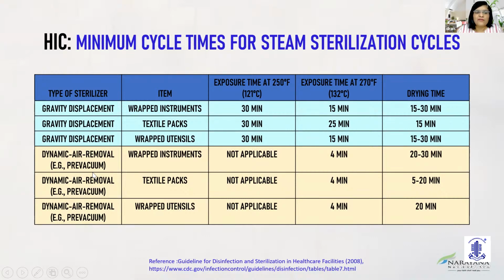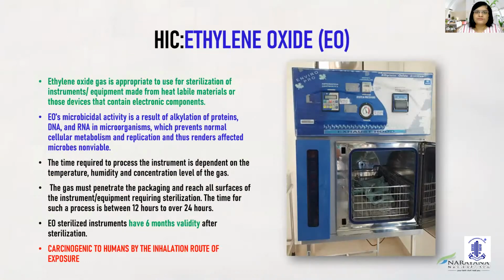However, if you have a pre-vacuum type of sterilizer, you can have these items, for example, wrapped instruments, textile packs, and wrapped utensils, where the exposure time is at 132 degrees centigrade, 4 minutes, and drying time is around 20 to 30 minutes for wrapped instruments, 5 to 20 minutes for textile packs, and 20 minutes for wrapped utensils. So this is how we can actually put our guidelines into place.